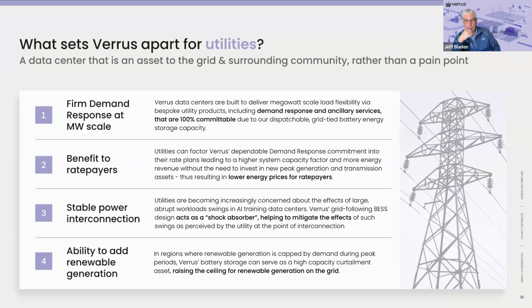And if I could just jump in and add one thing, an important distinction from what you were hearing a few minutes ago from our friend from California, is that this is not workload management. This is not taking activities in the data center offline. This is using the batteries and discharging them to keep productivity inside the data center while reducing stress on the grid. So it's really a win-win in that regard, and the asset backing is what allows us to do that.